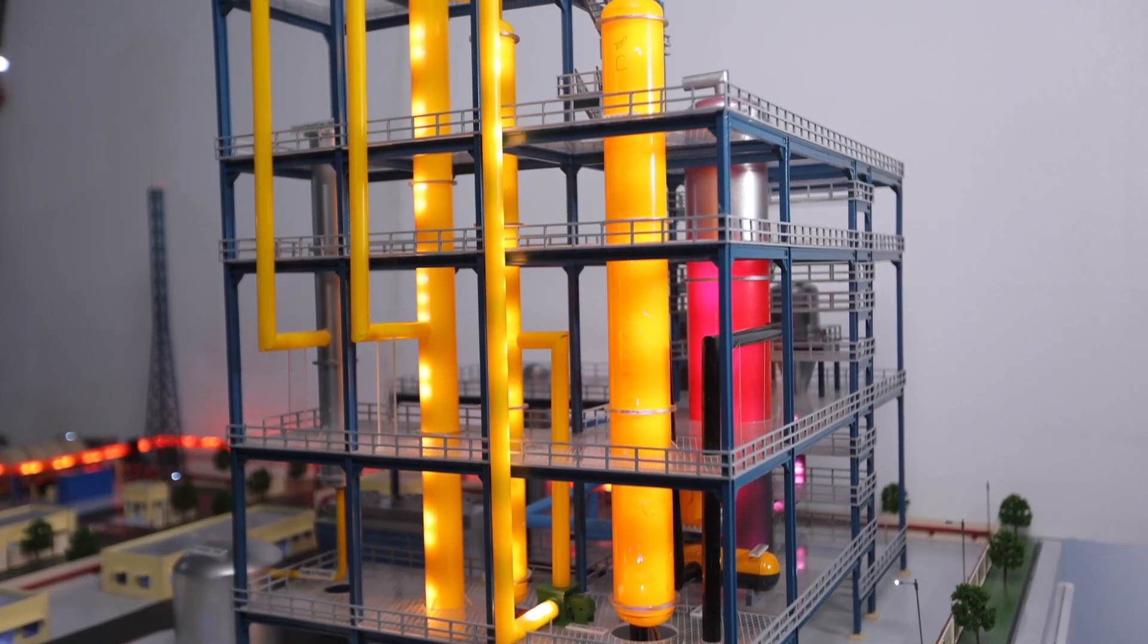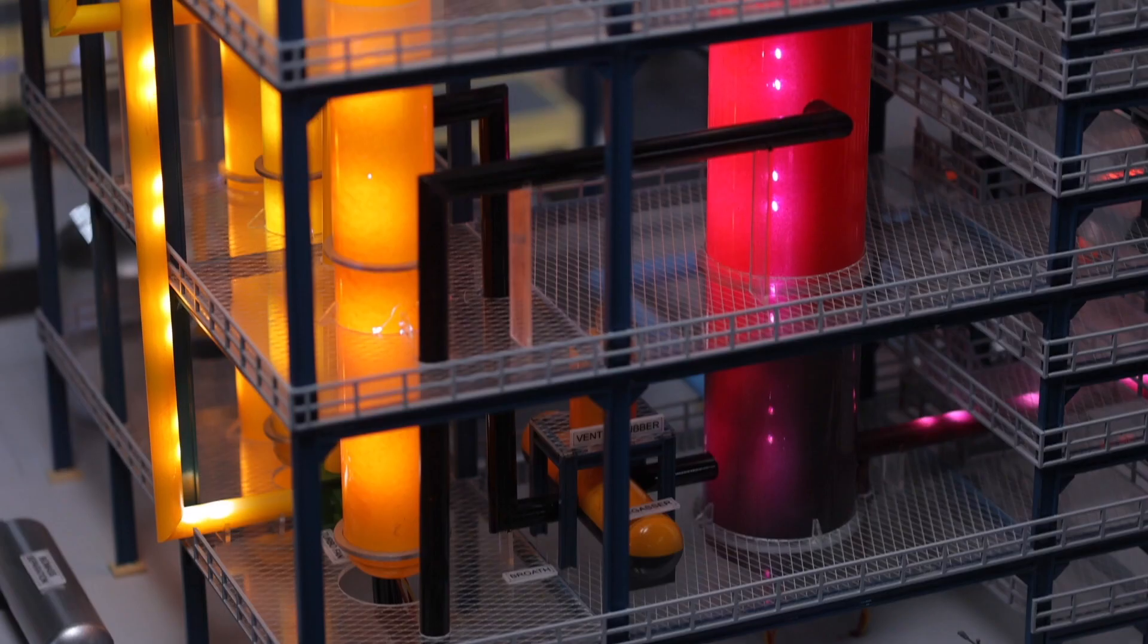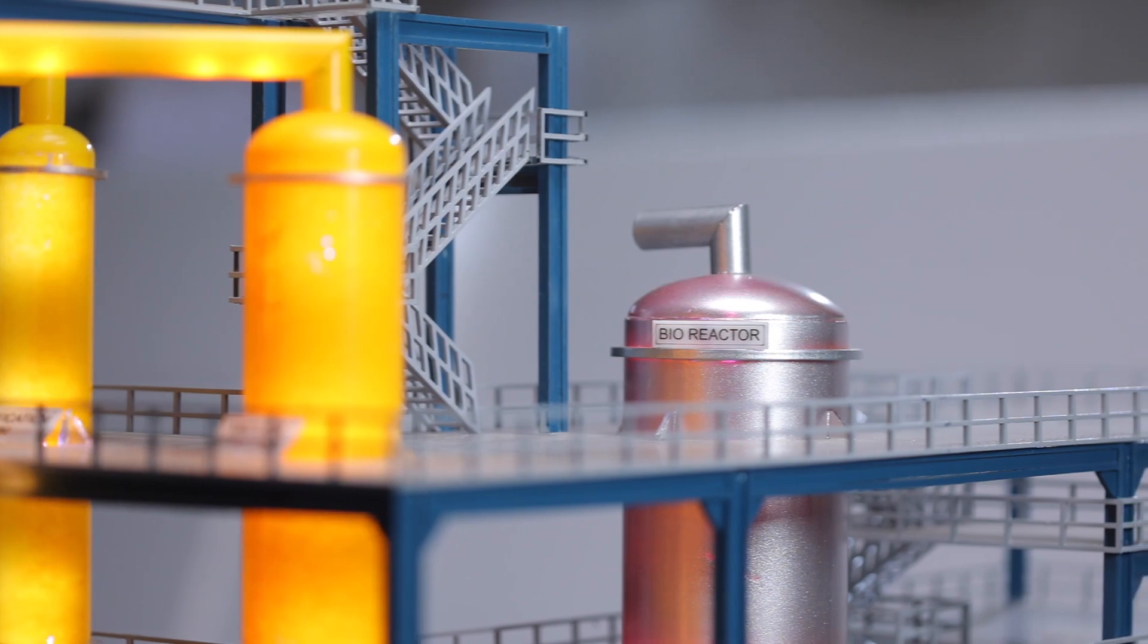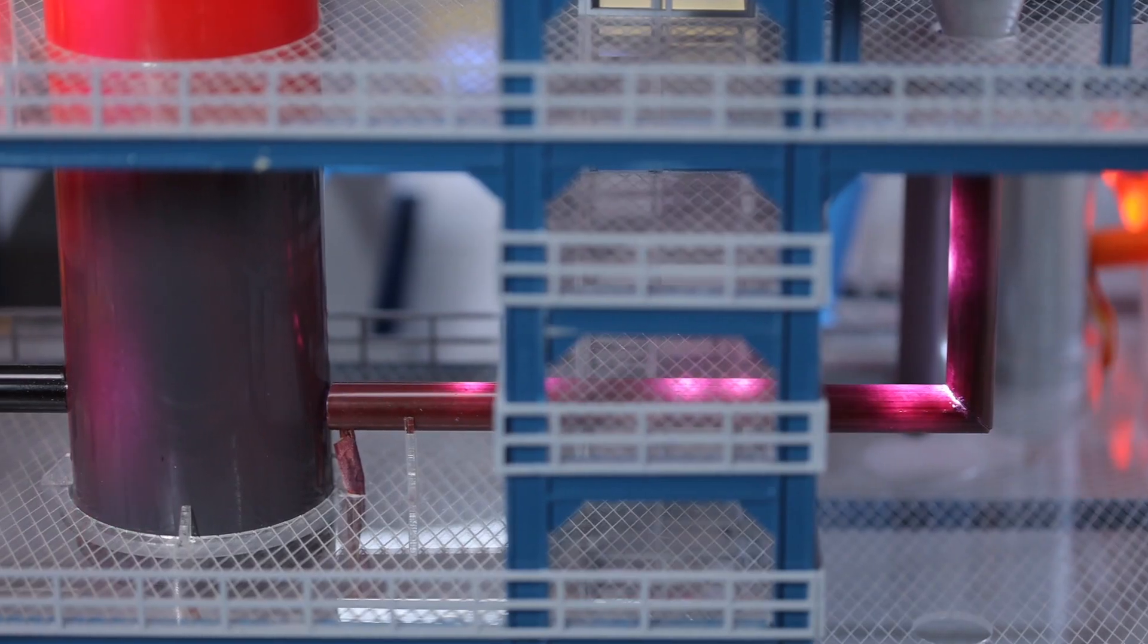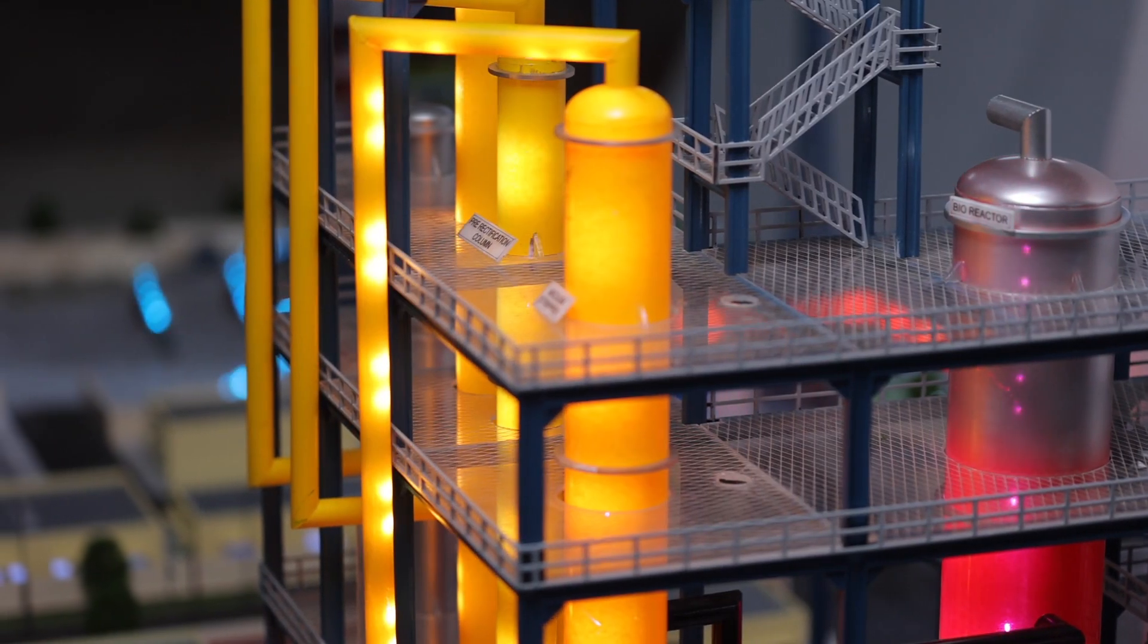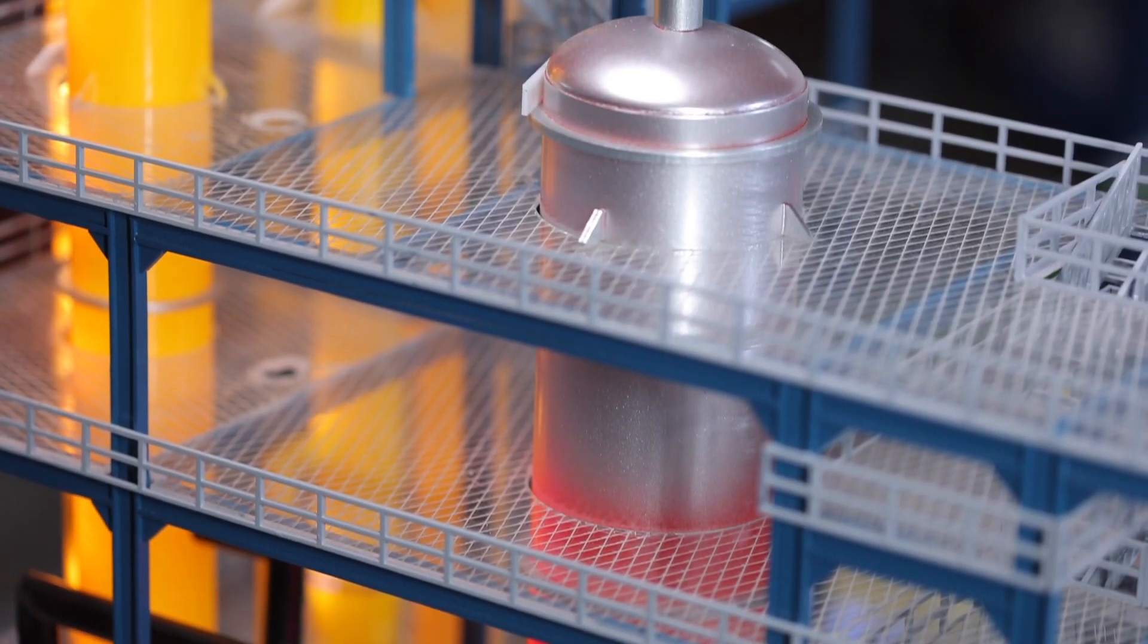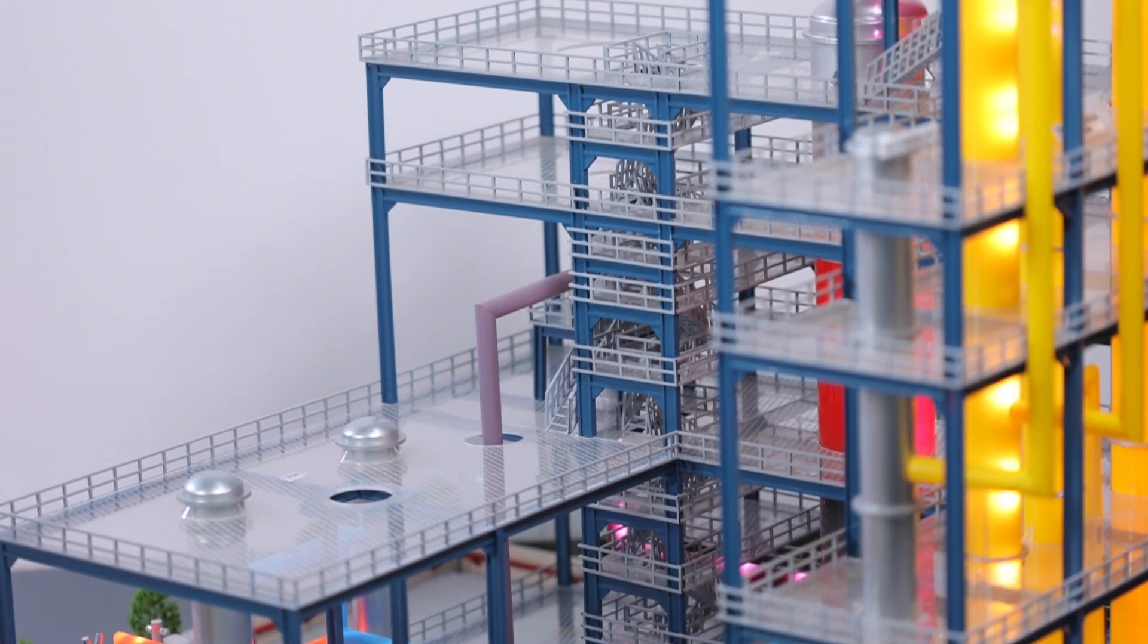Presynthesis: The syngas from gasifier enters into the CO2 capture unit, which will increase the CO concentration by CO2 removal through PSA adsorption method. The syngas from PSA unit will be directly fed into bioreactor. Cell Mass Activation: One tapping from output of PSA shall be passed through inline CO membrane, which will increase the concentration of CO by filtering out hydrogen for activation of biocatalyst in cell mass culture unit.